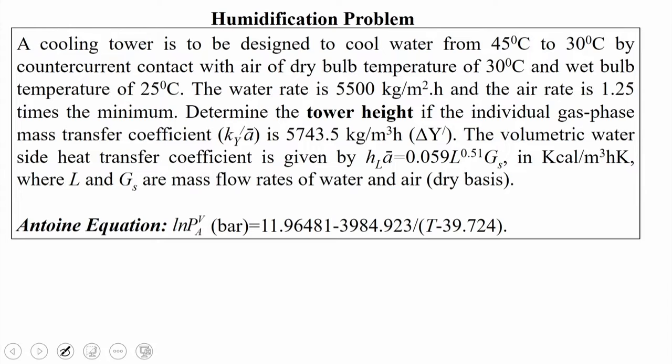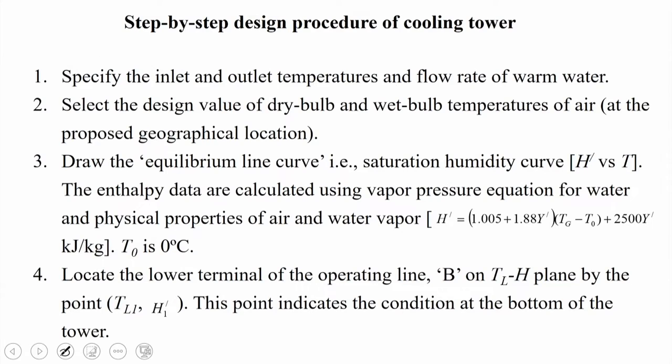Before starting the solution, we will recapitulate the step-by-step procedure of cooling tower design. The steps are: firstly, specify the inlet and outlet temperature and flow rate of warm water — in our case this is given. Then, select the design value of dry bulb and wet bulb temperature of air at the proposed geographical location — these are also supplied in this problem.